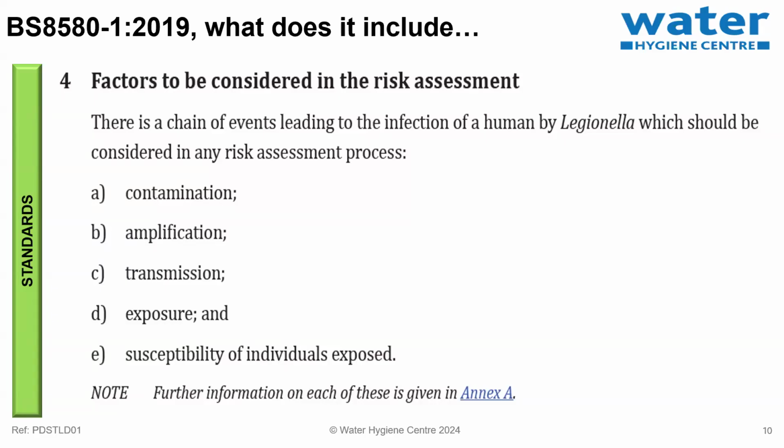So we're going to look at contamination. Legionella is a naturally occurring organism, and it's in mains water at low concentrations. How can a water system be contaminated or colonized, with nutrients in there to support it? Low flow or no flow equals a biofilm, for example. Do we accept that our water system, supplied via whichever utility provider, is not a sterile environment?